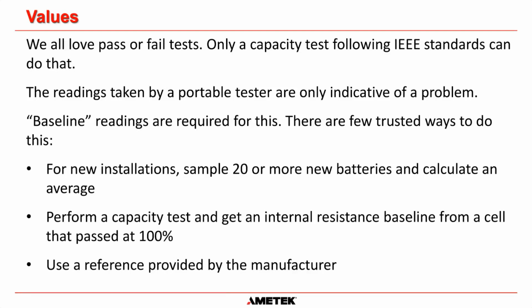The second way to get a baseline is to perform a capacity test, an IEEE capacity test, and then get the internal resistance baseline from a cell that passed at 100%. So what you should do before you do the test is take your readings using your portable tester. Then when you get the results back, you find one of the batteries that had 100%, and you look at your readings on your portable tester to see what the value of the internal resistance is on that cell or block, and that will be your baseline.